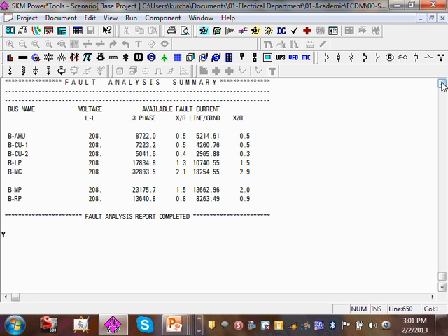Any comment, guys, about this short circuit calculation? You don't have a calculation at the transfer switch. Well, because I did not assign a point. You have to assign the points that you want. You can find the available fault current at any point. That's what the B is. The B is telling the system, I care about the point here. I just told the system at the time I didn't care about the point here. But you can imagine at the auto transfer switch, there's a circuit breaker ahead of it, so I can predict it's going to be around the MP 23 or so because there's a circuit breaker ahead of it. Okay, this is not the exciting stuff.